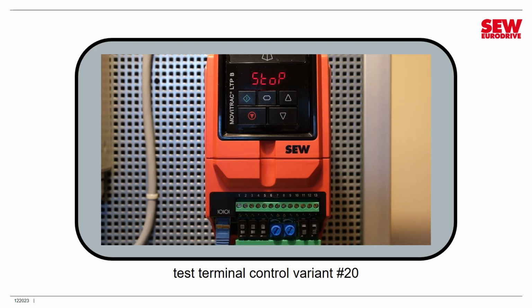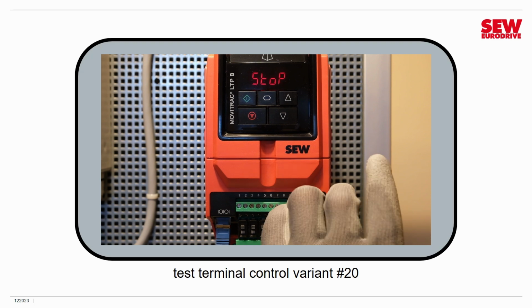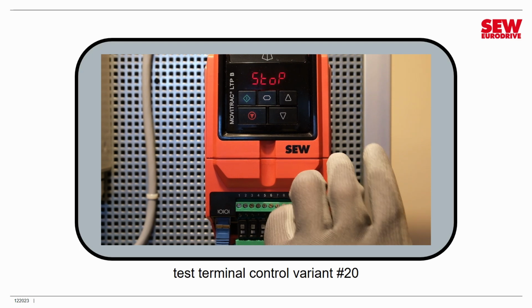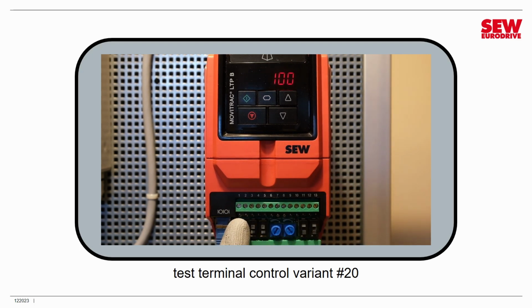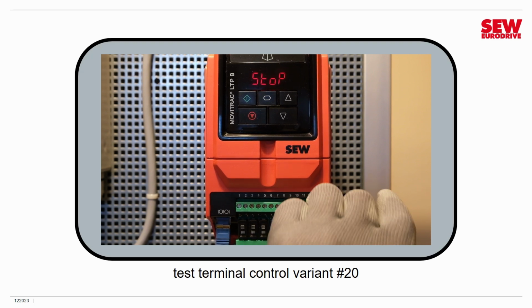Now we're going to activate our preset speed, preset 1, which is 100 RPM. I've got to turn digital input 5's potentiometer all the way up. And you can see just turning it on and off with digital input 1 or 2, we get the preset speed, and that's it.